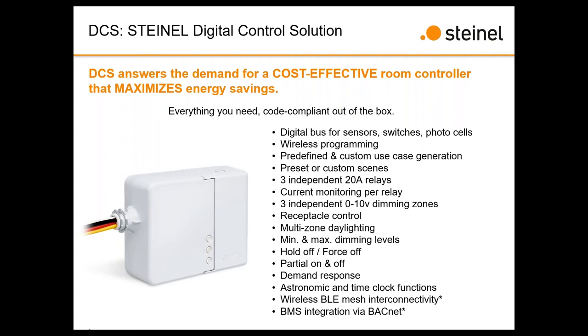Because I've got 3 relays, I can give you current monitoring on each relay. Most of the competitor product will give you current monitoring per controller. I've actually got the ability to give you current monitoring for each of those circuits. And of course, we've got 3 independent 0 to 10 volt dimming zones, which attach up to those. So you can do on, off, and dim up, down on those circuits. We've got receptacle control, as I mentioned, because they are each independently rated at 20 amp. We can control receptacles with those as well.